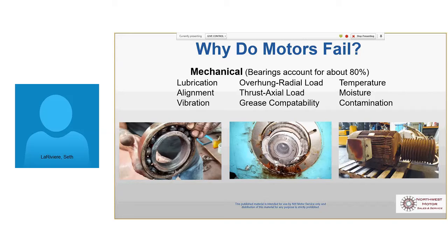So it's a pretty good sized motor before it even becomes greasable bearings. Well, it seems like half the time or more that you open up a motor, the bearings are sealed anyways. Sure. And it's got Zerks. They don't have a Zerk in the grease seal bearing. Right. You know, the reality is if you've got a 100-horse motor that's lost its bearings, and that's the only thing wrong with it, it's just bearings, you're still kind of looking at it's cheaper to get a new motor than even just do the bearings, you know, even at 100 horse.